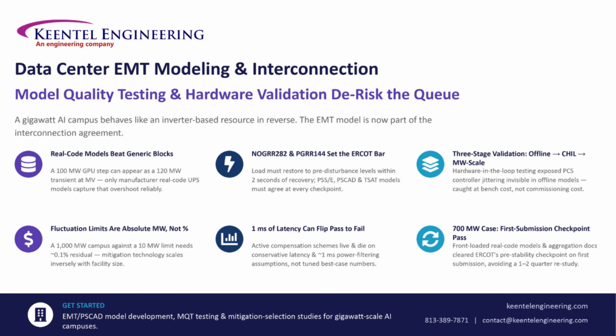In ERCOT, NOGRR 282, and PGRR 144 have made this concrete. Load has to restore to pre-disturbance levels within 2 seconds, and PSS/E, PSCAD, and TSAT models all have to agree at every review checkpoint. Getting there takes real validation, not just simulation. Offline EMT catches the electrical fundamentals, but hardware-in-the-loop testing is what exposes the defects offline models can't see. In one real project, it caught controller jittering during grid forming to grid following transitions that the OEM had originally denied until the bench evidence proved it.